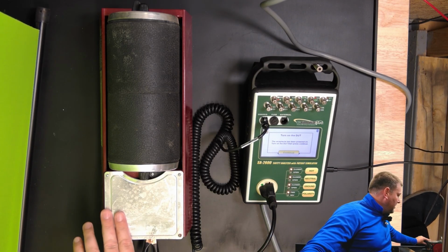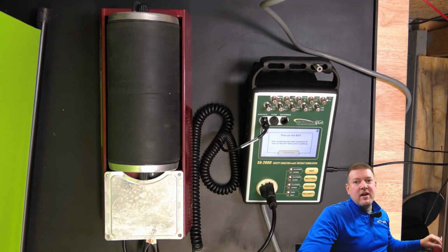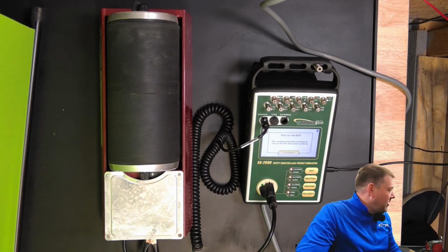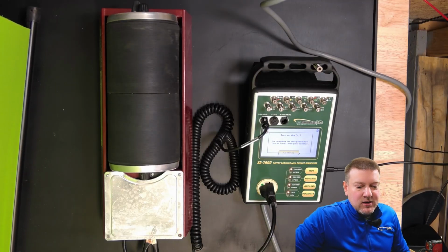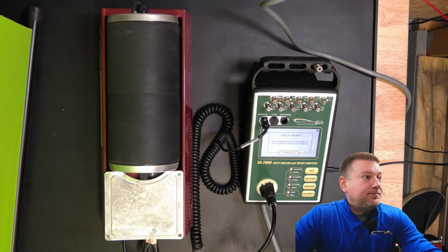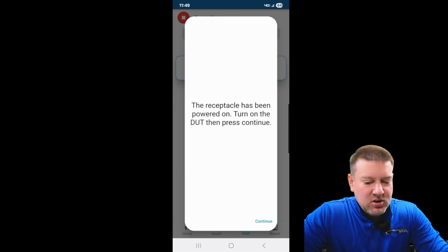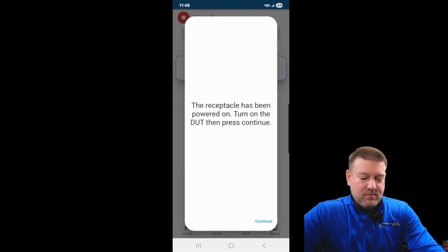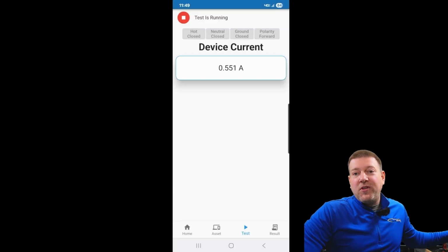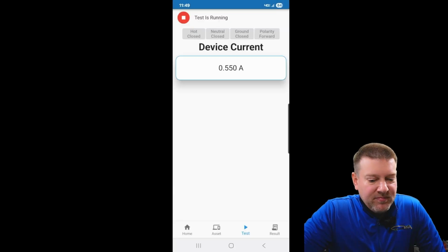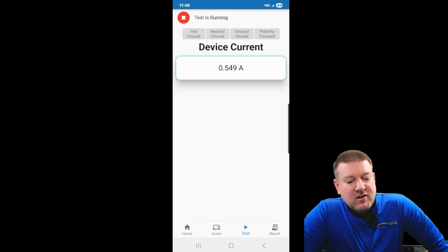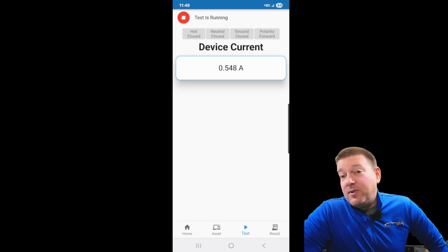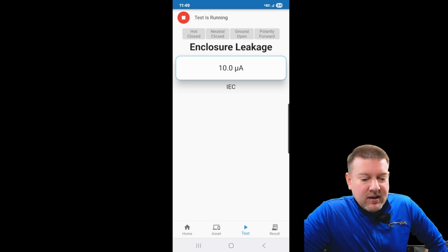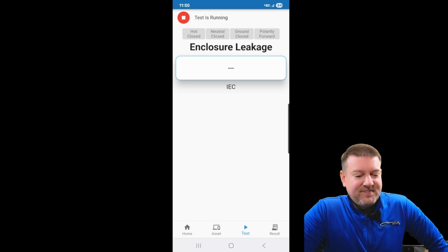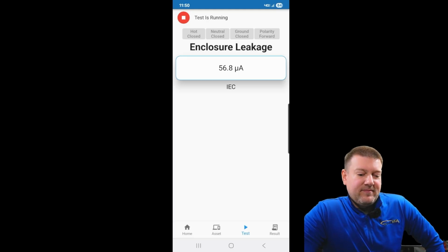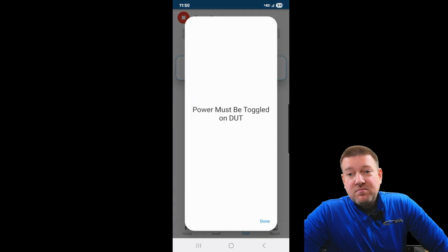Okay, so it says turn on the device. So here is where you turn on a device, activate any fans, heaters, pumps, or whatever, and then you can go ahead and continue. Now, on my mobile device, you can see that it's saying the receptacle has been powered on, turn on the device, press continue. So I'm getting instructions both on the SA-2600 and here on my mobile. And you can see it's pulling a device current of 0.55 amps. That's pretty good. And it's now taking leakage checks. 56 microamps. Not too bad.